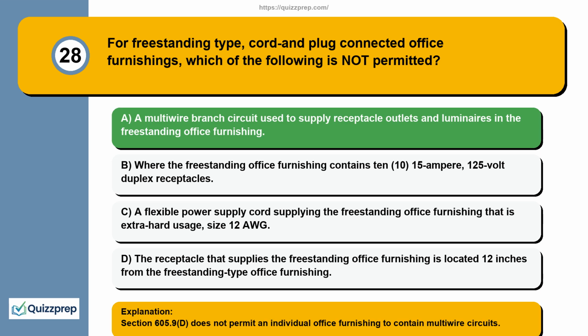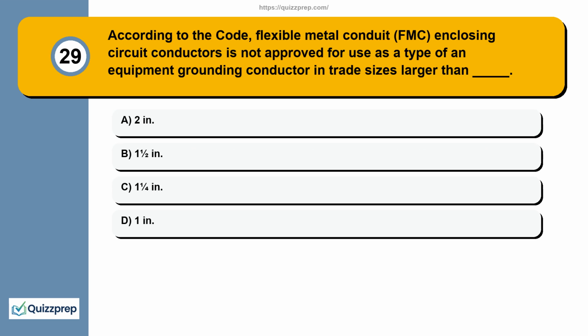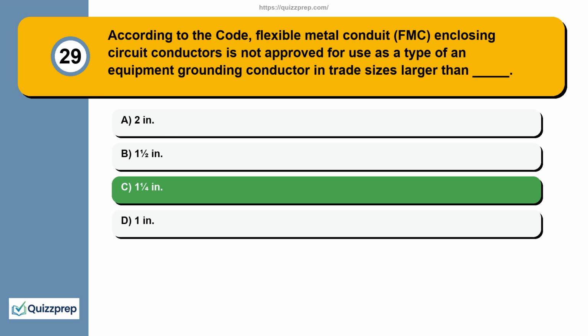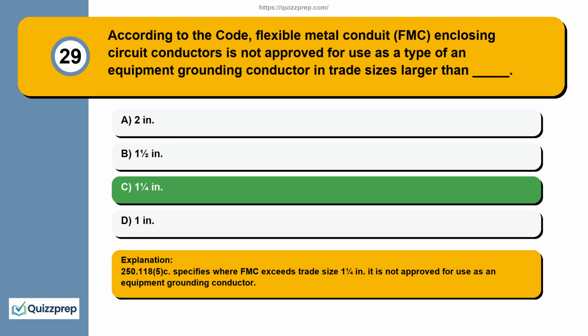Section 605.9(D) does not permit an individual office furnishing to contain multi-wire circuits. Question 29. According to the code, flexible metal conduit (FMC) enclosing circuit conductors is not approved for use as a type of equipment grounding conductor in trade sizes larger than: 2 in., 1½ in., 1¼ in., 1 in.. 250.118(5) specifies where FMC exceeds trade size 1 1/4 inch, it is not approved for use as an equipment grounding conductor.